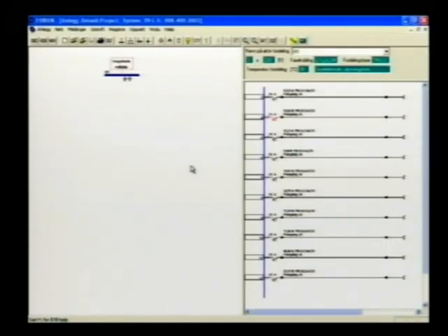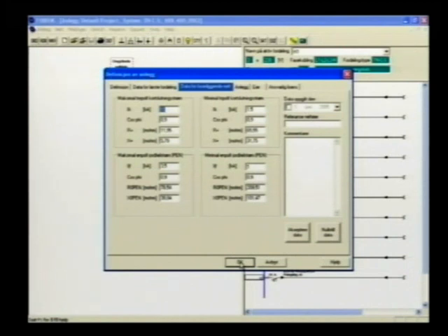So what we do is that we import the IFC model, which I have got from the electro partner. We import it, and of course we only extract the information that we need for the use of FEBDOK, which is not the graphical model. It's not used. But we take the information we got, and that is mainly the circuit list from the outcircuits from the switchboard. Already now I can see that because of this red protection device, something is wrong.